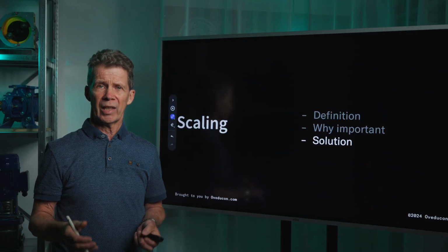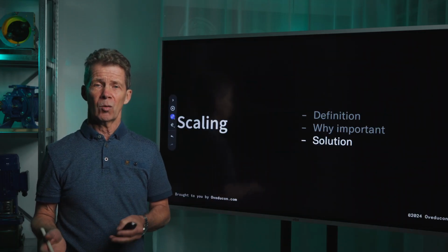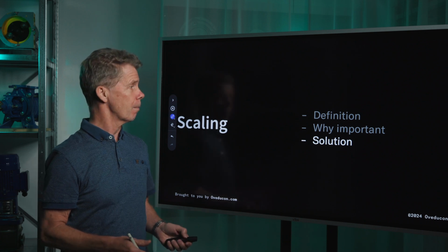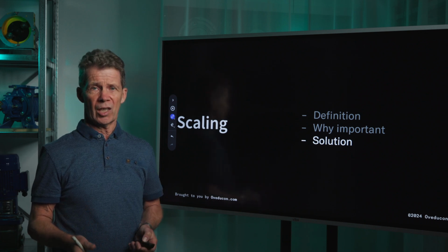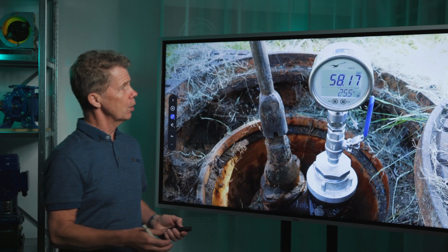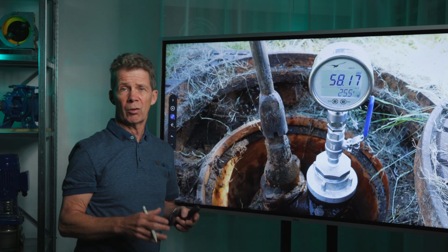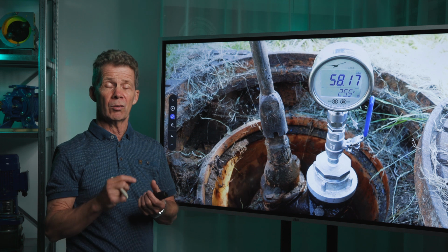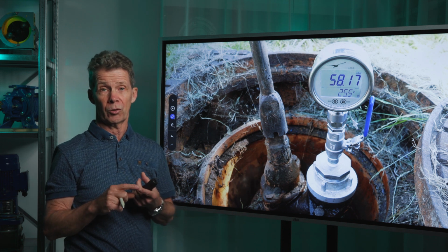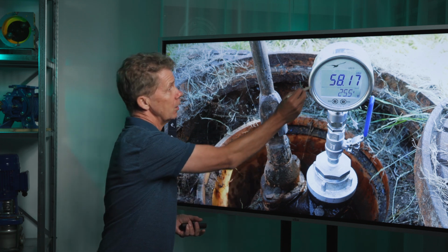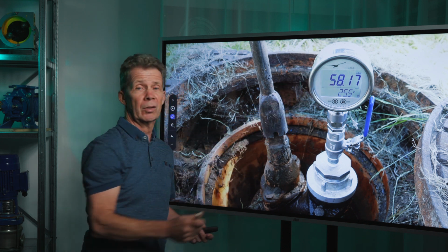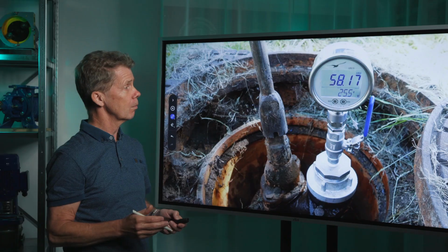But how to recognize scaling and what is the solution? To recognize scaling, put on a pressure gauge on your system. And do that on your suction line and also on your discharge line. And here you see your pressure gauge reading. Do it on a regular basis and you will know if your pressure is changing.